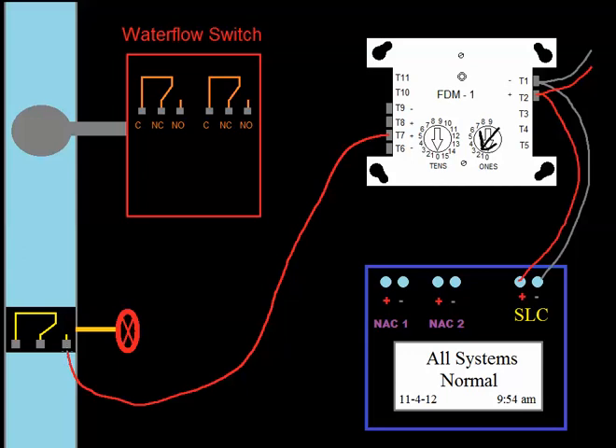So the valve tamper is just a normally open contact device. So this would be my normally open contact. I'll take terminal 6 down to common and I'll put my resistor across there.